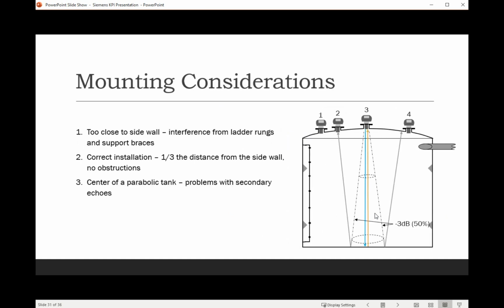And number 3, this one would not be a good mounting area on a parabolic tank. You'd get a good return off your liquid, your water, but then you'd also have problems with secondary echoes. It would bounce off the top of the parabolic tank, and then come back down, hit your media again, and then reflect back into the transducer, causing secondary echoes maybe 2 or 3 times down the road, and sometimes could have a higher signal strength than your actual level and your actual media.